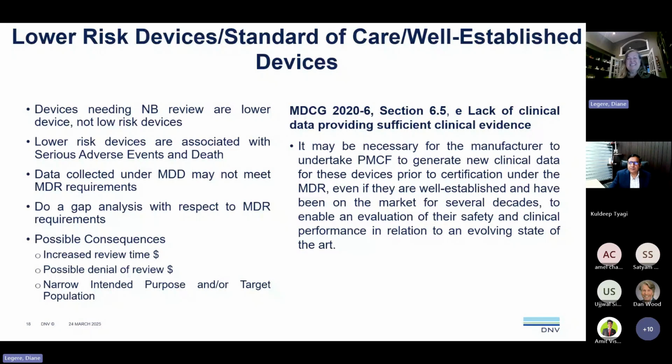I heard a beep. Yeah, I think that's a good point, Dan, which you raised here. And I think a lot of manufacturers, in my experience, struggle. They see that, hey, my device has been doing really great, and we have collected data from MAUDE database and others, and very few adverse events. But as you rightly mentioned at the beginning of the presentation, you cannot really 100% trust that data because it has not been adequately reported, right?